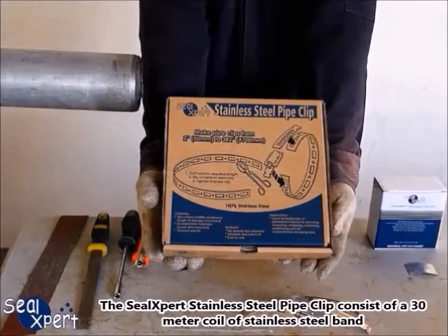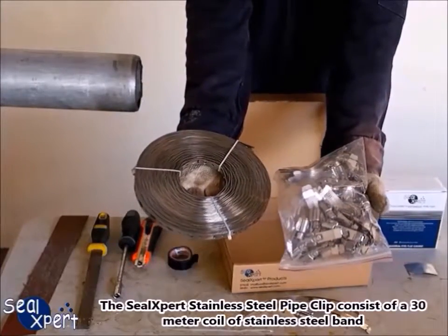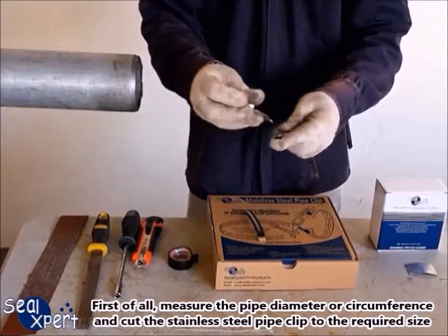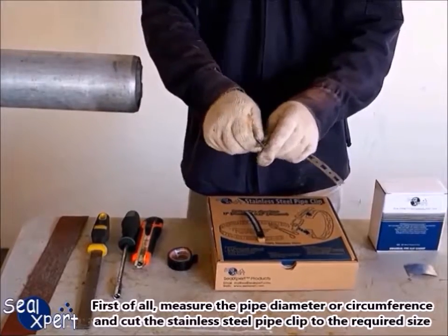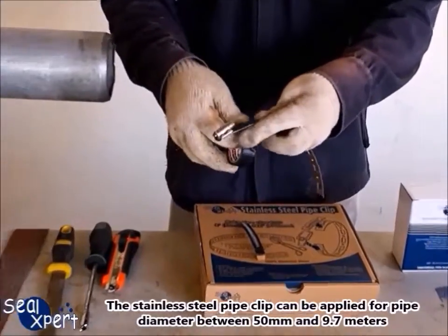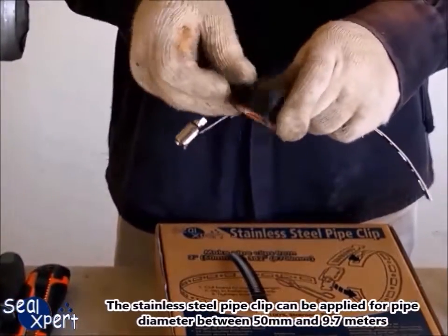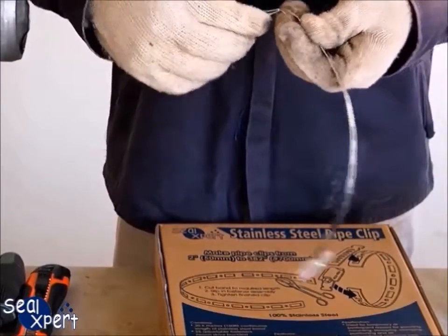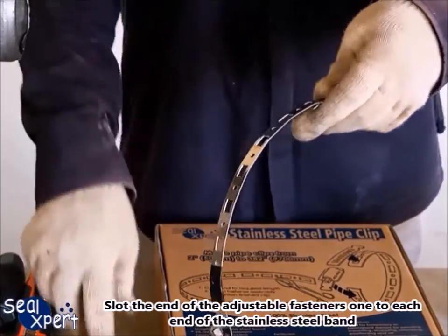The SealXpert stainless steel pipe clip consists of a 30-meter coil of stainless steel band, 25 sets of adjustable fasteners, and 10 pieces of splices. First, measure the pipe diameter or circumference and cut the stainless steel pipe clip to the required size. The pipe clip can be applied for pipe diameters between 50 millimeters and 9.7 meters. Slot the end of the adjustable fasteners, one to each end of the stainless steel band.